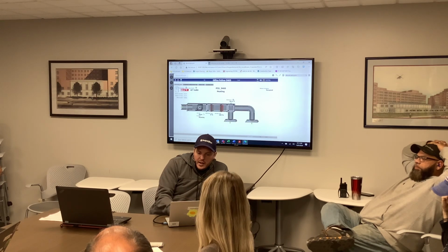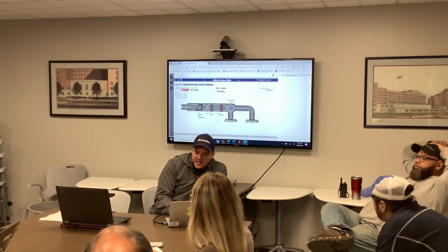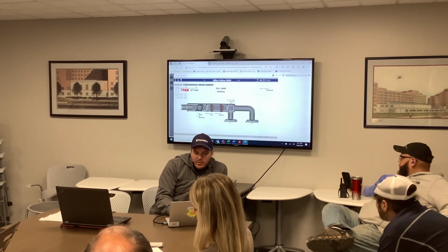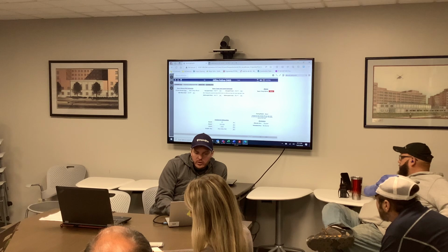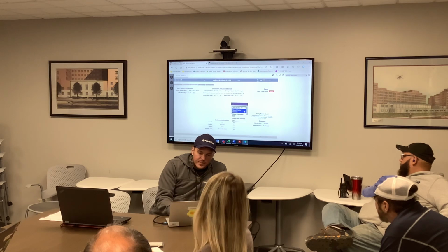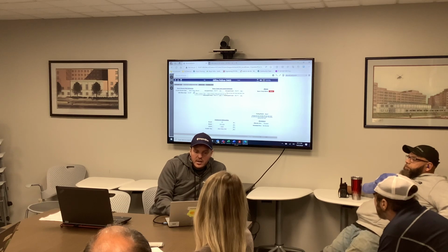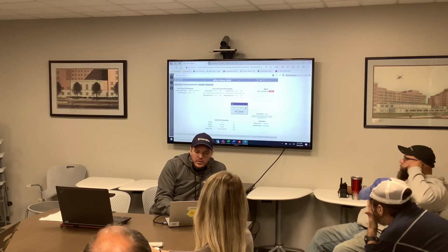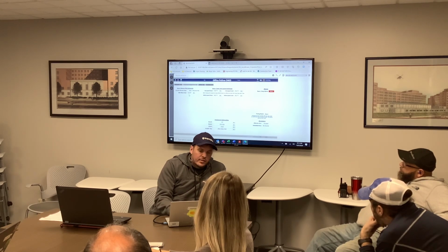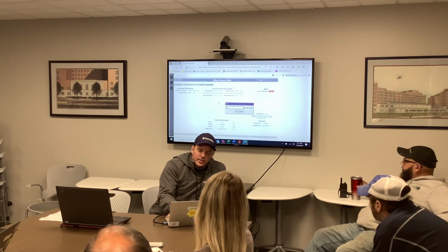Alright, moving on. This is pretty basic, none of this stuff is overrideable, it's just stat and integration control, so you just need to do set points. For the end user or the local user, if you wanna disable this stat, you can right click on it and set it to no set point, and this way they can't change any set points. If you do allow them to do set point adjust, they're only allowed to move it up or down 5 degrees. You can set that here, so you can say you're allowed to set it, but only by 2 degrees.